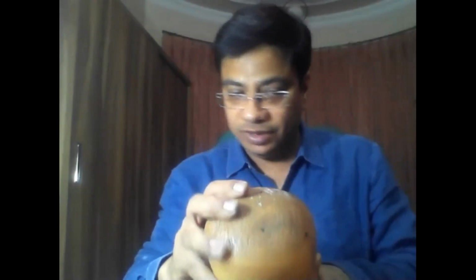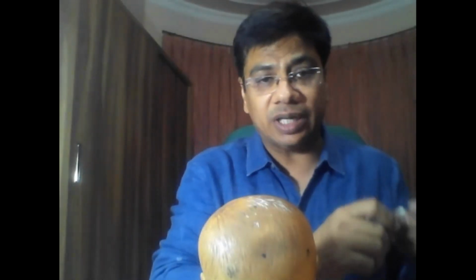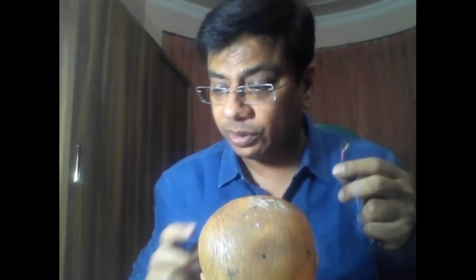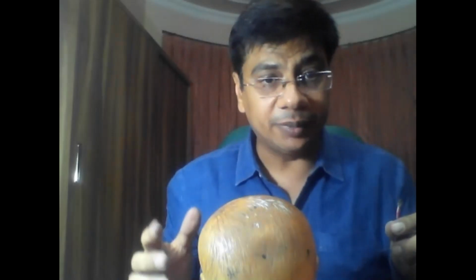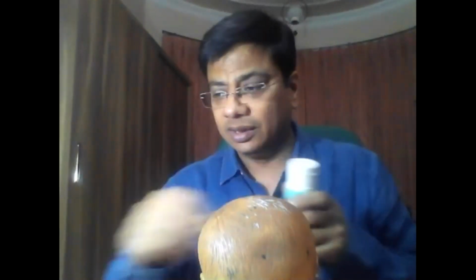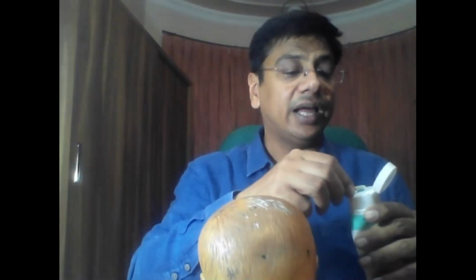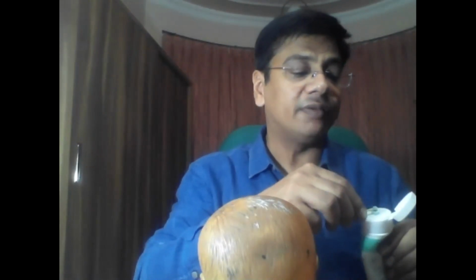Once we have located the landmarks, obviously we need to place the EEG electrode, which has to be a gold plated electrode because gold plated electrodes have good conductivity. They are good conductors, and we need to have an impedance which should be less than 5 kilo ohms. So we have to clean first where we have located the landmarks. We need to clean these landmarks as well as clean this dust which can be on the scalp to have a better conductivity.